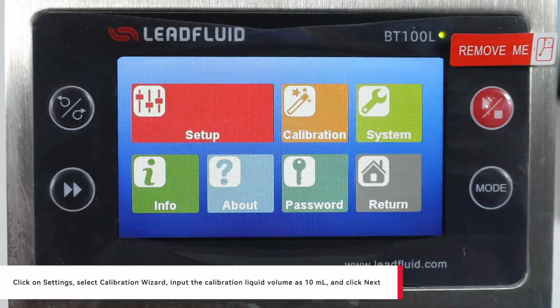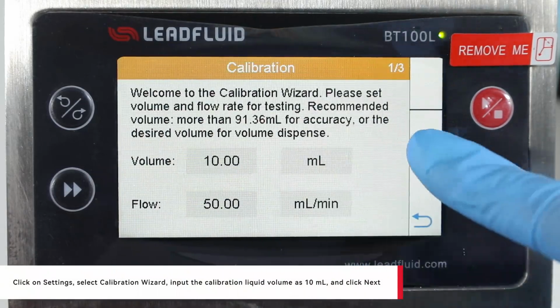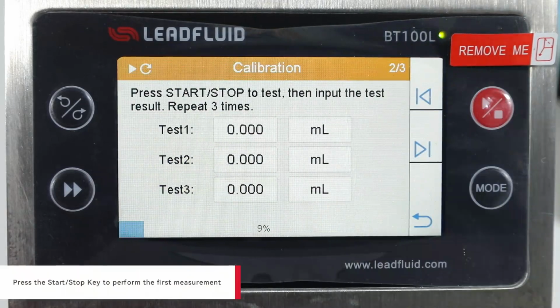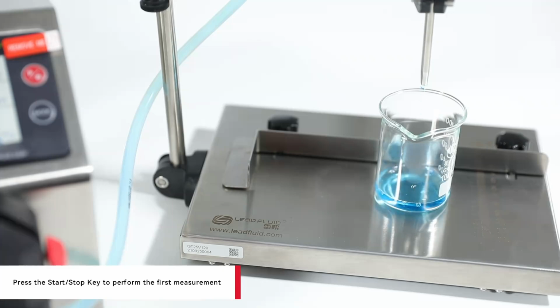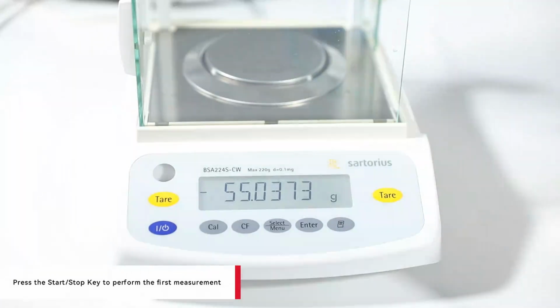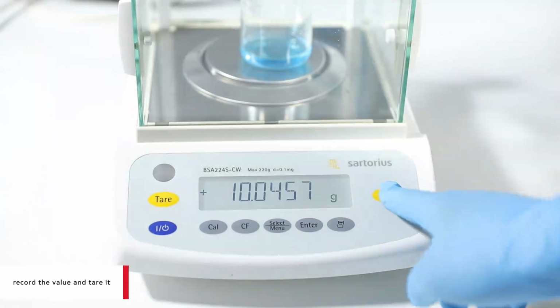Click on Settings, select Calibration Wizard, input the calibration liquid volume as 10 milliliters, and click Next. Press the Start or Stop key to perform the first measurement. Record the value and tare it.